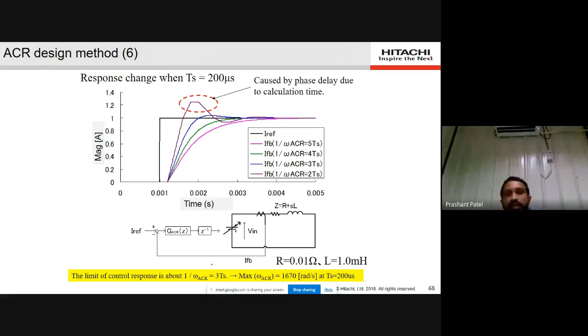This is just a summary of AVR and ACR for this converter. Now we have designed the AVR controller and the inner ACR controller. The D-axis controller controls your phase shifting, it controls delta, and is responsible for the active power transfer between converter and grid. This is the Q-axis controller, responsible for the amplitude change between the converter voltage and the grid voltage, and based on that it transfers reactive power.